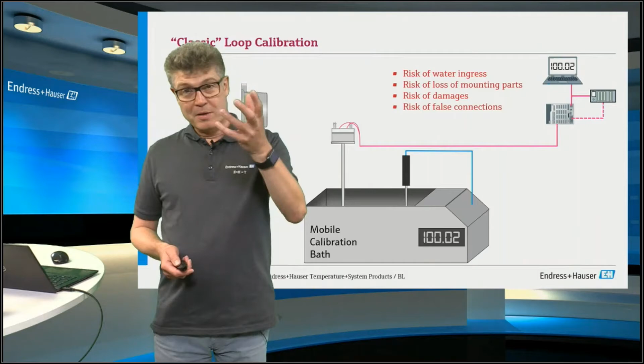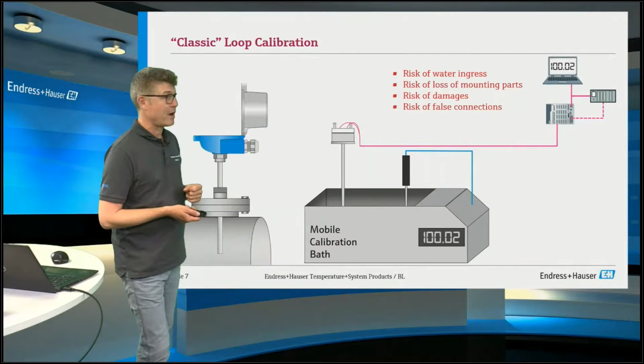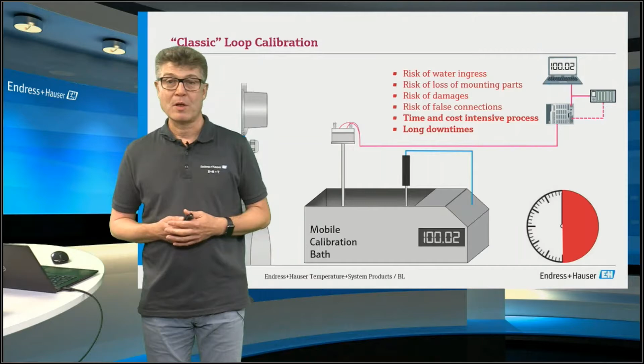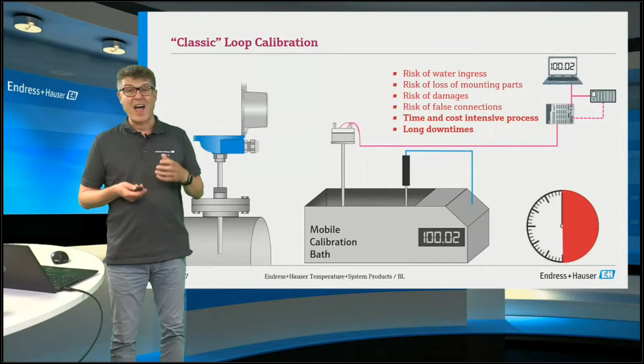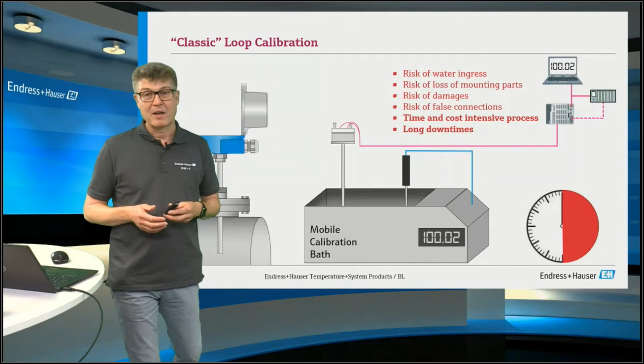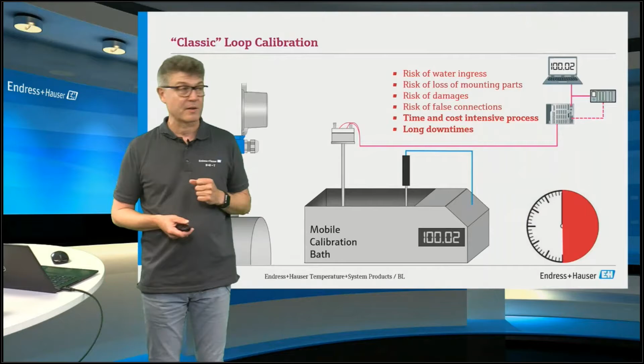So customers ask us, this is a lot of work. We don't like it. Please, dear Endress and Hauser, what can you do for us? Because on average, it takes us 30 minutes of production loss for every instrument to perform a calibration. So think about how often you calibrate, and how many instruments you have in your plant, how many critical control points. It depends. A small dairy maybe has 20 or 30. A big life sciences company might have 1,600. And then it's really important how often you do a calibration.